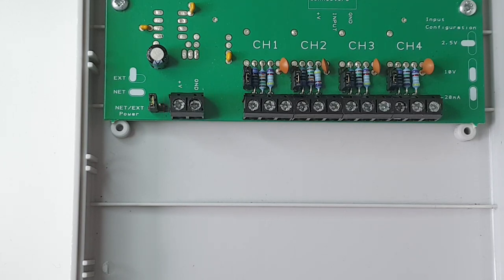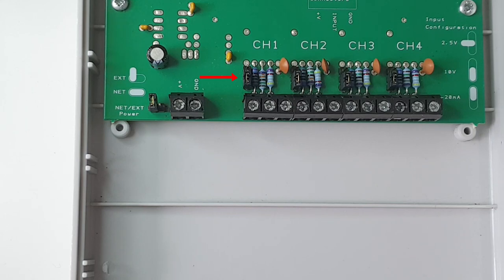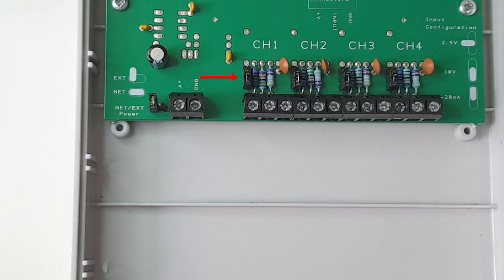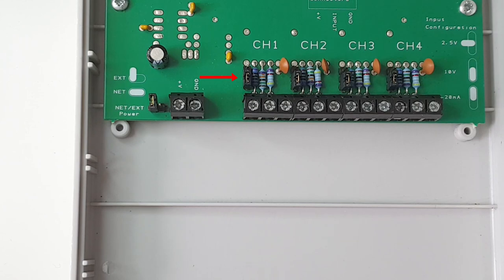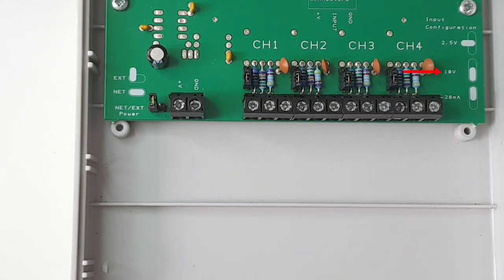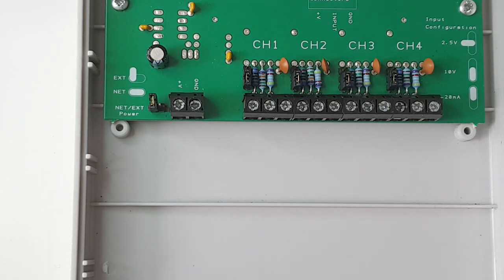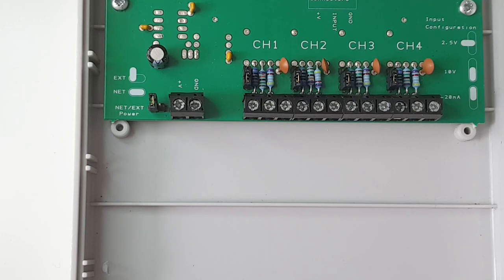Now you'll see above the terminals for the channels that each of them has a jumper. So this means we can adjust each of the channels to either take a 4-20 milliamp signal, a plus or minus 2.5 volt range, or a plus or minus 10 volt range. At the moment all the channels are on the bottom two pins that are shorted, which means they're on the plus or minus 10 volt range.